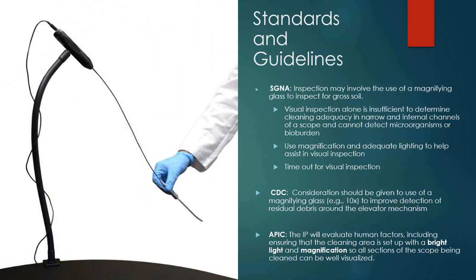You would need something this detailed in magnification because of the small detail at the distal tip with the lever. APIC, the IP, will evaluate human factors, including ensuring that the cleaning area is set up with bright light and magnification, so all sections of the scope being cleaned can be well visualized. So IP, you might want to go look at your SPDs and see if there is some type of magnification in doing this.